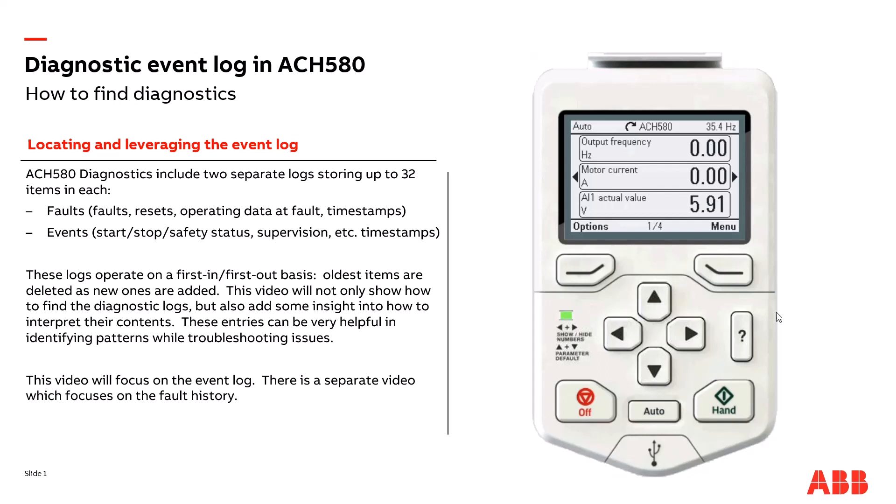The difference between these logs is that one records faults and the other records events. Faults are conditions that cause the drive to stop modulating, such as over-current, DC bus over- or under-voltage, over-temperature, short circuits, and things like that. Events are transitions in operating state such as start, stop, safety interlock opening, hand-off-auto transitions, etc.